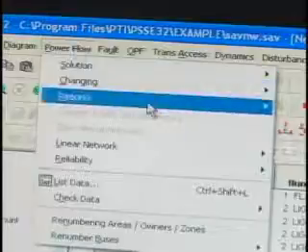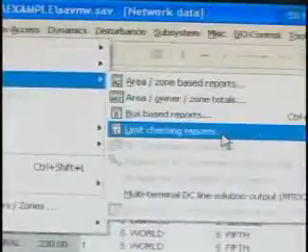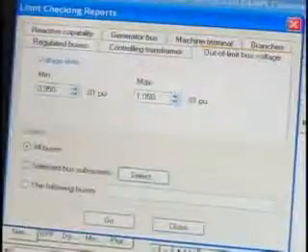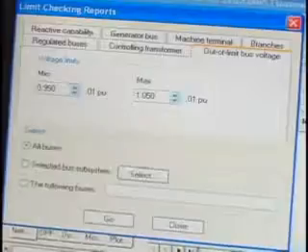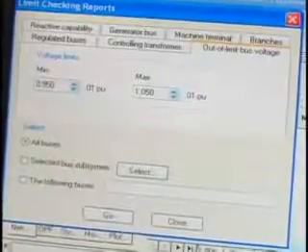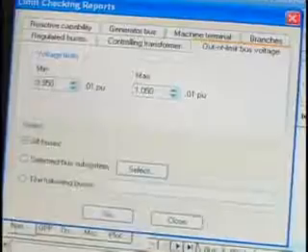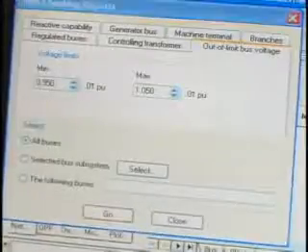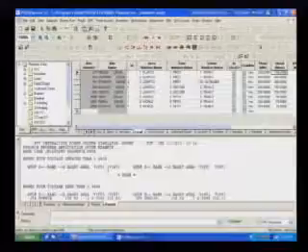Let's go to the last step, reporting, to help you understand the network condition. There are many reports that you can run. Let's go to Power Flow, Reports, Limit Checking. Let's check on a very common application, voltage, to see if any voltage is beyond plus minus 5%. That means minimum 0.95, maximum 1.05 per unit. Click Go. You can see a new report comes up.